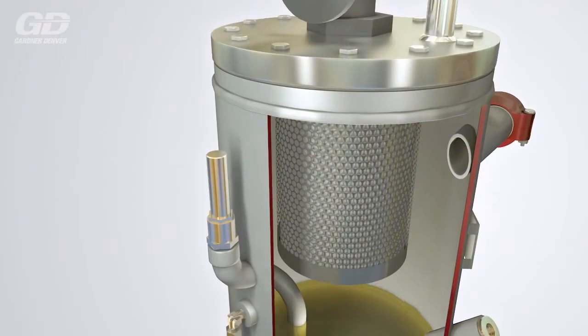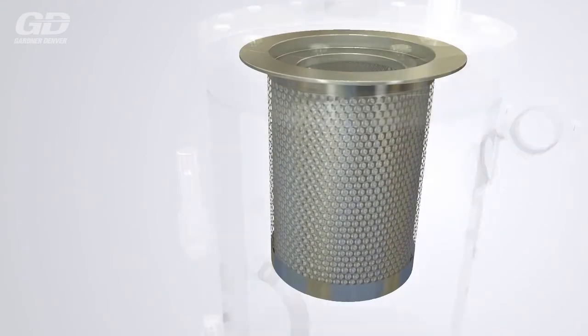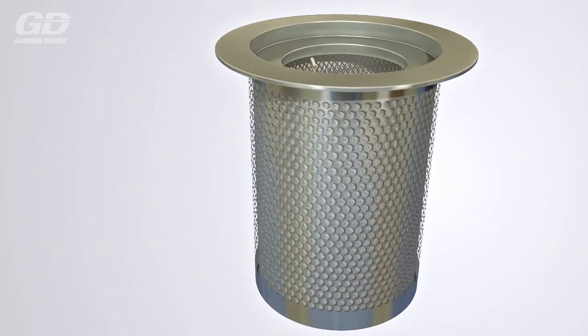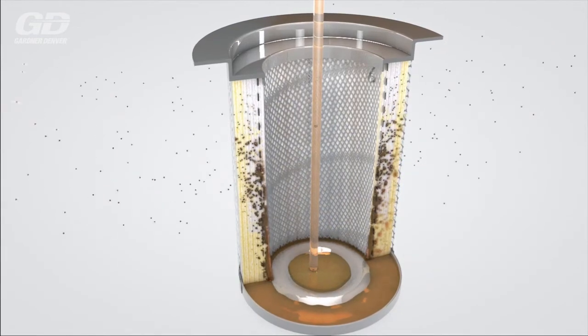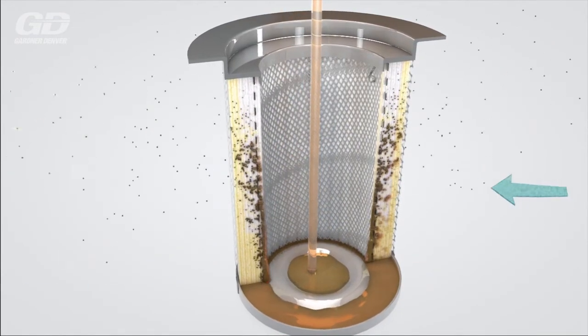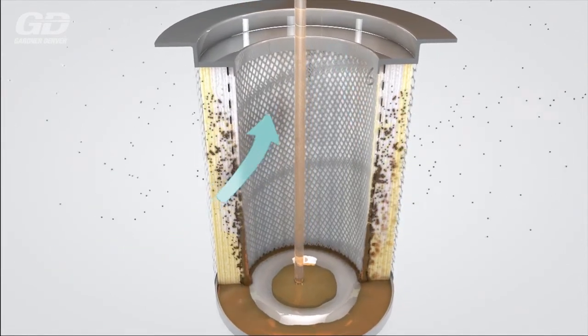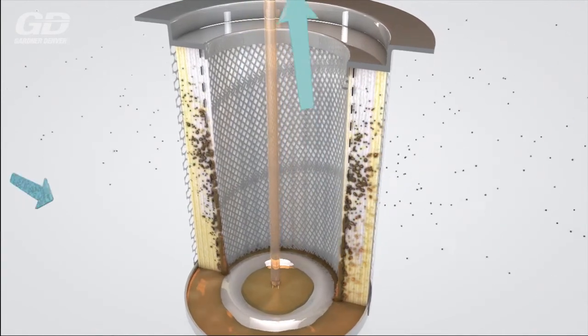In order to achieve a residual oil content of one to three parts per million, a further separation process is necessary. Therefore, the oily air now flows through the air oil separator. In the layers of filter media, many smaller oil droplets are converted to larger oil drops through the coalescing effect and then sink to the bottom of the filter.